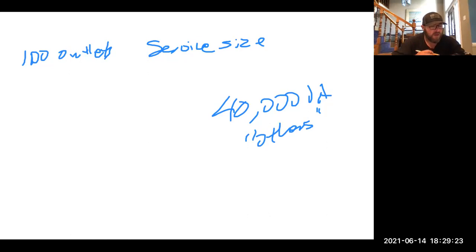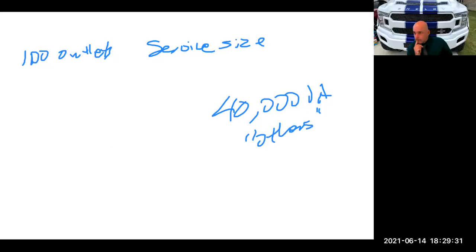Receptacle outlets shall not be calculated less than 180 volt-amperes for each single yoke. Right. As a branch, that's absolutely true. That would be the minimum calculation, and there wouldn't be any derating in the branch. You'd have to provide 180 VA for every receptacle on every branch circuit. So all your branch circuits effectively would be 100% of your total number of receptacles per circuit, at 180 VA.